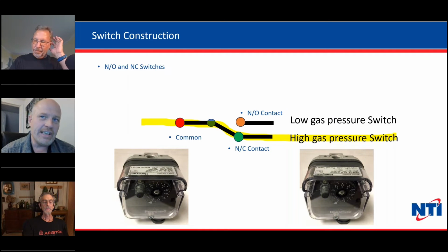The idea behind this switch is that if that pressure ever gets too great, meaning that somehow the valve is passing too much fuel, it will trip the switch. Now, in reality, with a negative pressure regulated gas valve like the one that we use, and the setting that's used on that switch, they will never trip under any condition that I can think of, except for some sort of backfire event on your boiler. If your boiler has a very rough ignition, it can create a pressure pulse that's strong enough to come back and trip a high gas pressure switch. But in virtually any other case, there's really nothing that should trip it. It's almost impossible for that to occur. So unless you're really, really unlucky, you're just never going to see that.